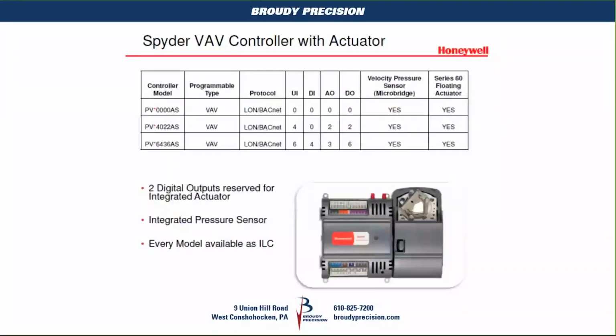In the VAV controller, they come in the LON flavor, in 3 essential model numbers. Again, you're looking at a programmable VAV, and the top one you see there is the 0000AS VAV controller. I'd like to briefly discuss the beauty of that particular model. Now, you may be sitting there wondering, what good is this particular model if I have no I/O available? A lot of cooling-only VAV applications or VVT applications only require an actuated damper motor with a space temperature sensor.